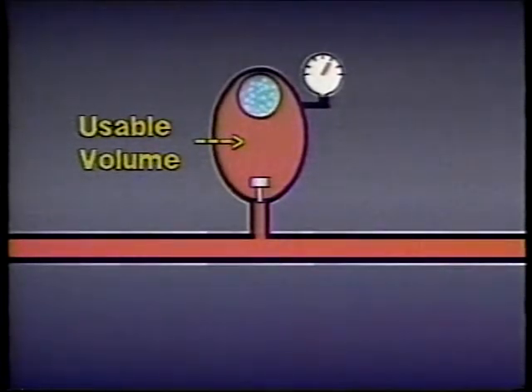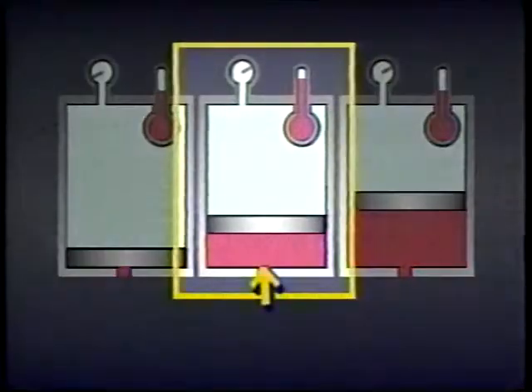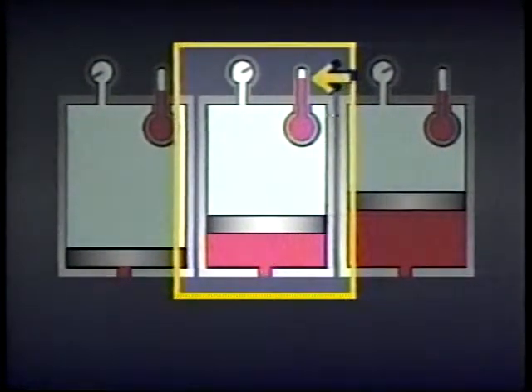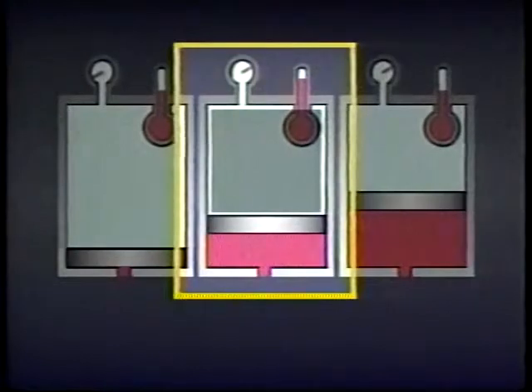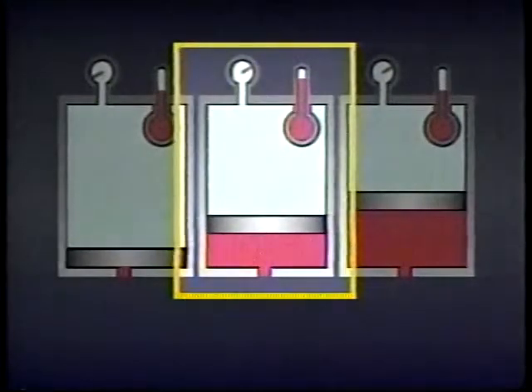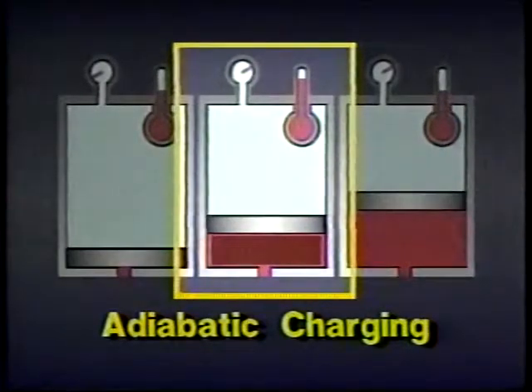The usable volume in an accumulator depends on how quickly the accumulator is filled with fluid, how rapidly it is discharged, and on the pressure of the pre-charged gas. When an accumulator is filled with fluid quickly, the gas pre-charge heats up as it compresses and so it occupies more space in the accumulator than if it had remained cool. The more space the gas pre-charge takes up, the less usable volume there is for the fluid to occupy. This is called adiabatic charging.